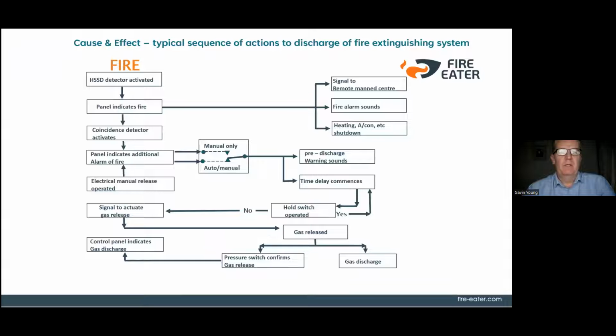So the sequence of operation here is, you've got a smoke detector that is activated. It operates the panel. From the panel, it generally shuts down dampers, sends a signal to a monitoring station, and operates the fire alarm system within the building. When a second detector activates, it creates a second alarm on the panel and operates a pre-discharge. Then the time delay operates, and generally, as I said, it's 30 seconds. There's normally a hold button or an abort button at each exit to the room or the risk. Once you press that hold button, it starts the 30 seconds again. It goes back to 0 and starts the countdown again. This is to allow anybody in the room to get out.